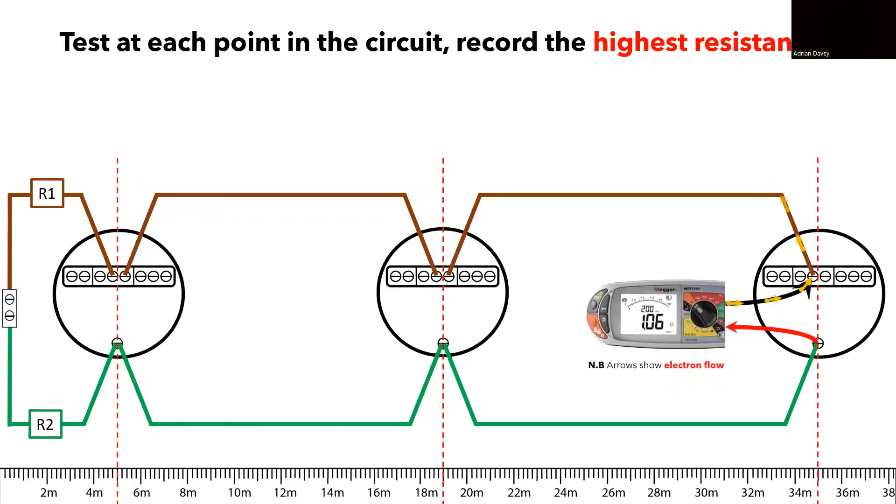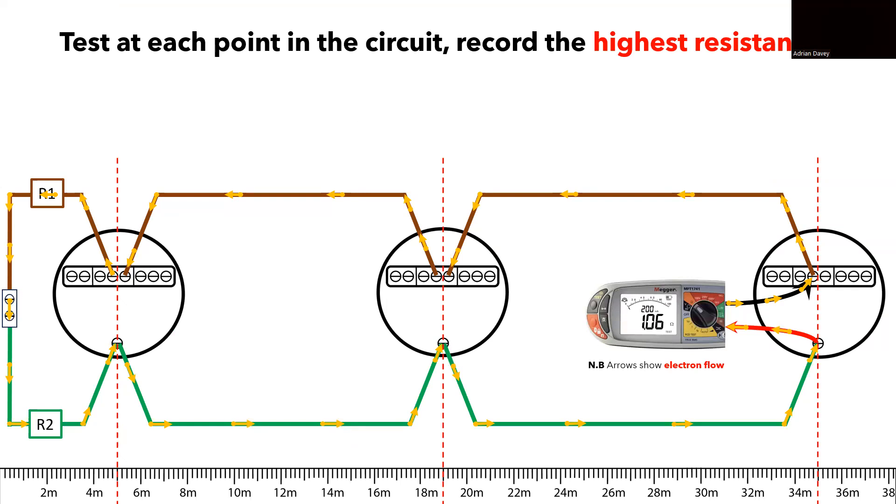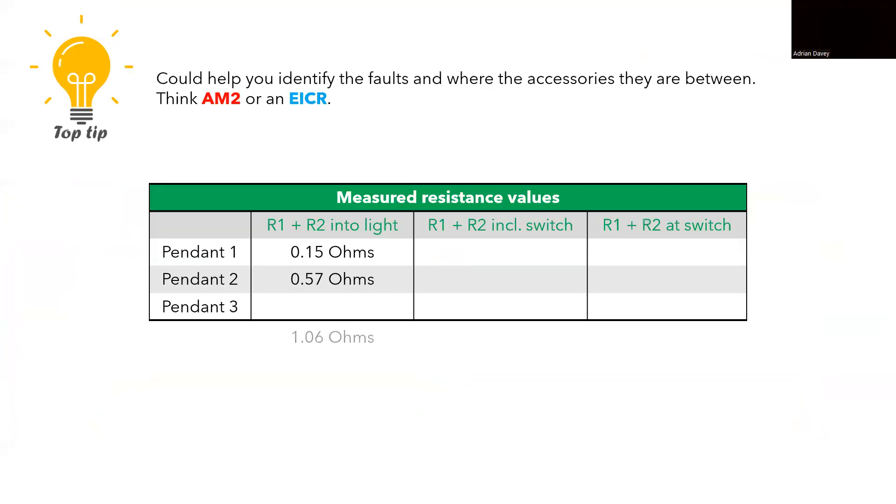Finally, we arrive at the last point in the circuit where we encounter the longest length, resulting in a reading of 1.06 ohms on our MFT. For the last distance, which is 35 meters, the calculated value is approximately 1.057 ohms, which we can round up to 1.06 ohms. We've now successfully confirmed that the supply remains uninterrupted throughout the entire circuit, extending to the last point. We should now include this measured value in our results table.